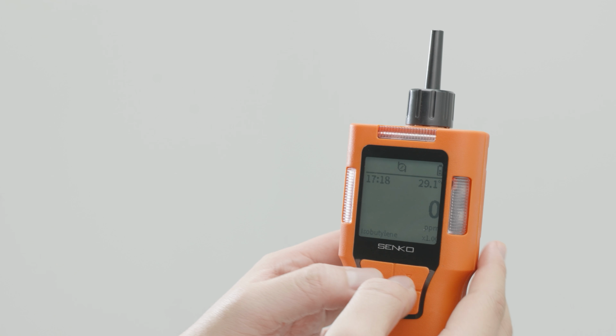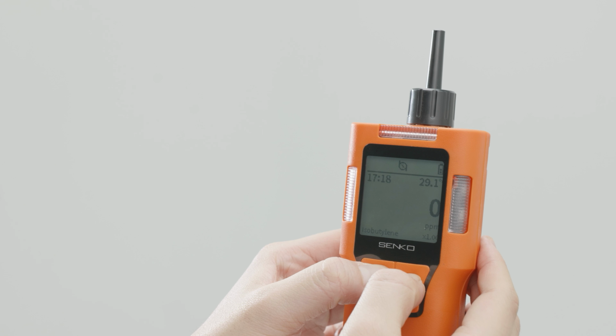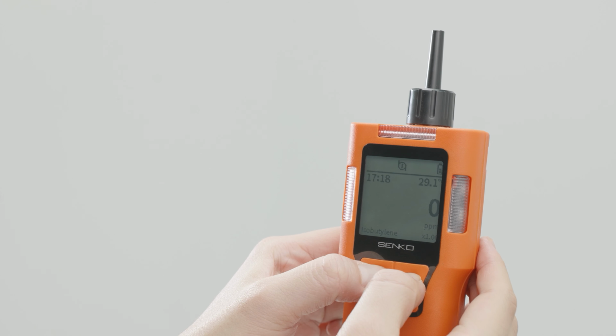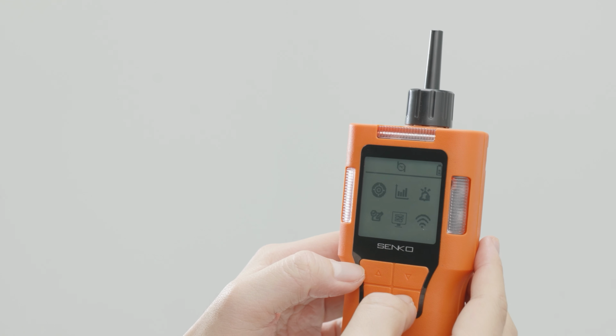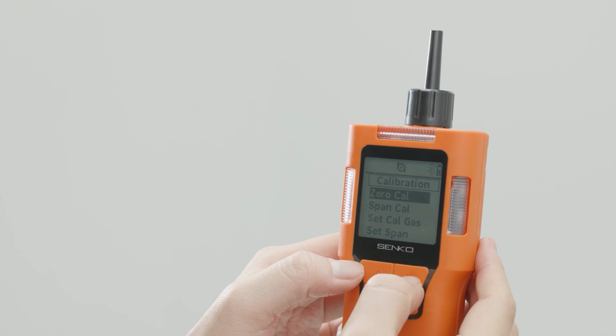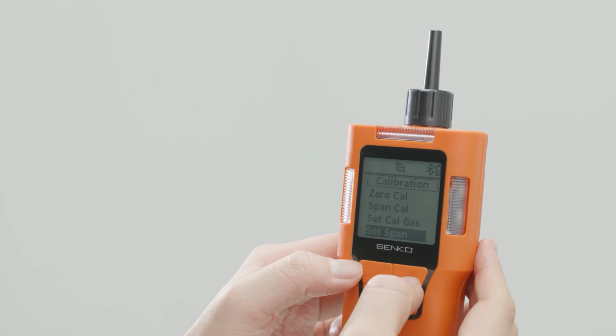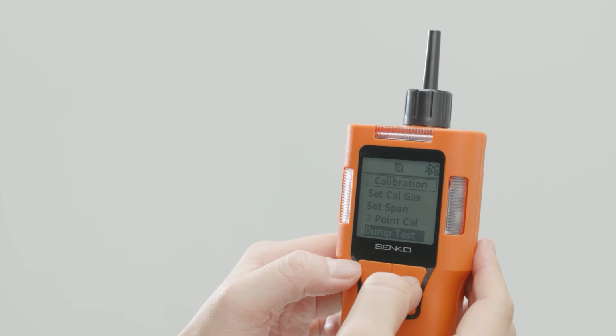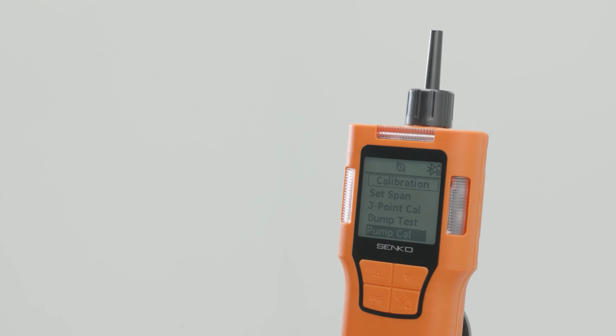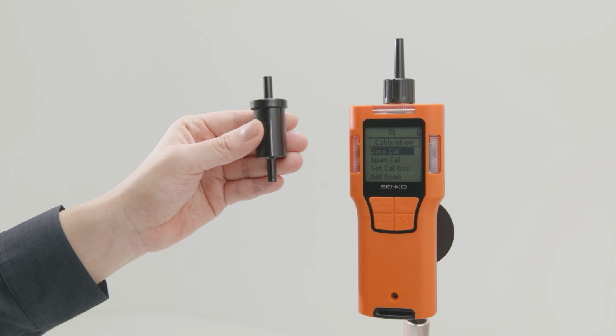In calibration under the settings menu, you can select 0, span, or span 2 and then press the Enter button to start. Depending on the calibration method, it takes about 10 to 30 seconds, and when calibration is completed, the result is displayed on the screen as done or fail. The calibration interval can be set from 1 day to 365 days, and it can be managed through Senko IR link. vPro supports the following calibration methods.